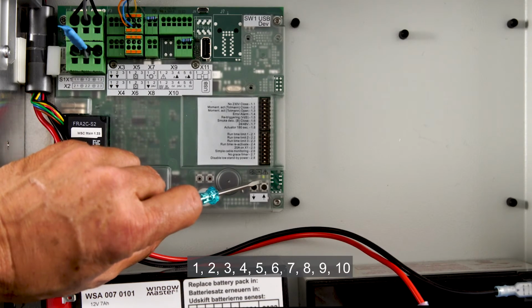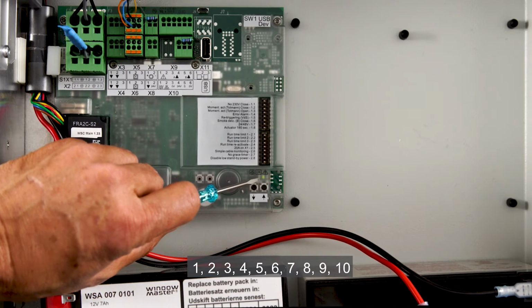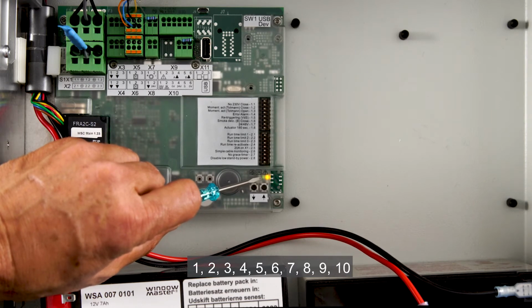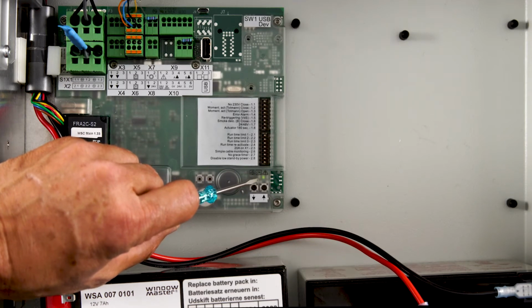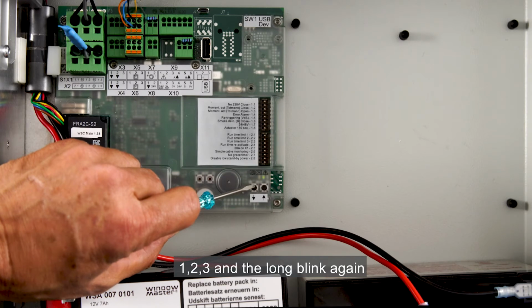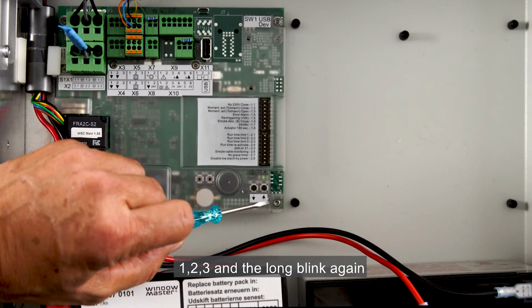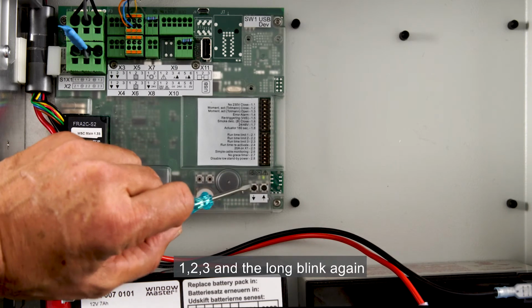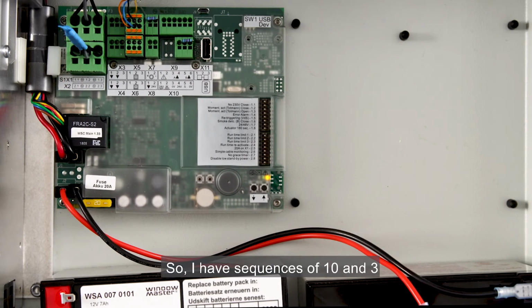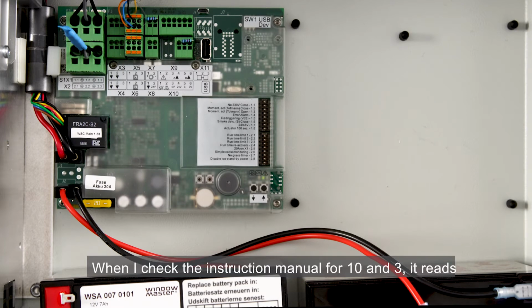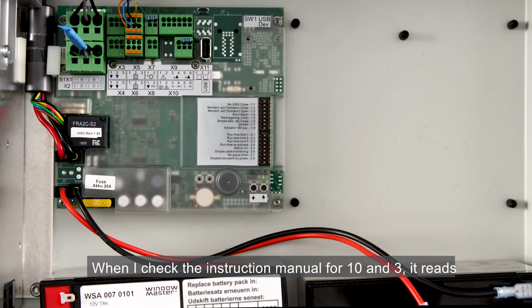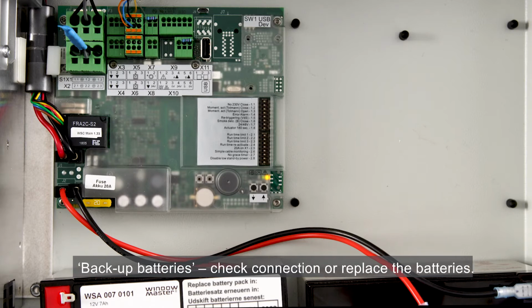1, 2, 3, 4, 5, 6, 7, 8, 9, 10, 1, 2, 3, and the long blink again. So I have sequences of 10 and 3. When I check the instruction manual for 10 and 3, it reads backup batteries, check connection or replace the batteries.